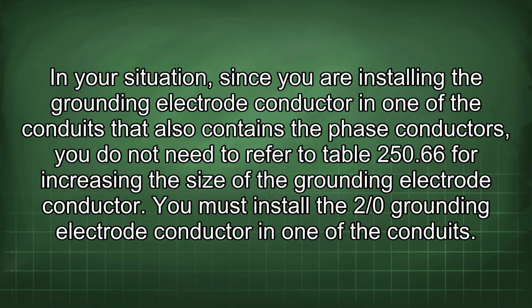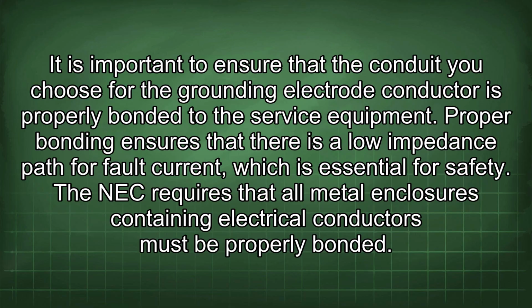In your situation, since you are installing the grounding electrode conductor in one of the conduits that also contains the phase conductors, you do not need to refer to Table 250.66 for increasing the size of the grounding electrode conductor. You must install the 2/0 grounding electrode conductor in one of the conduits. It is important to ensure that the conduit you choose for the grounding electrode conductor is properly bonded to the service equipment. Proper bonding ensures that there is a low impedance path for fault current, which is essential for safety.